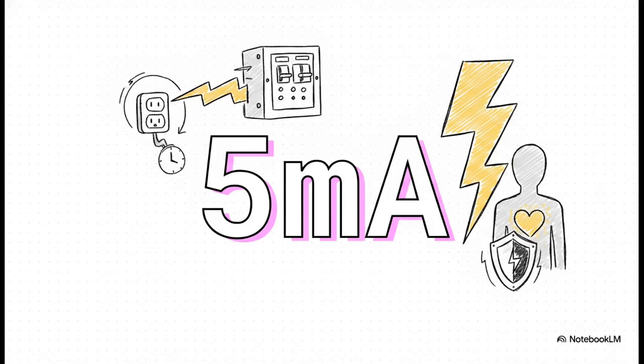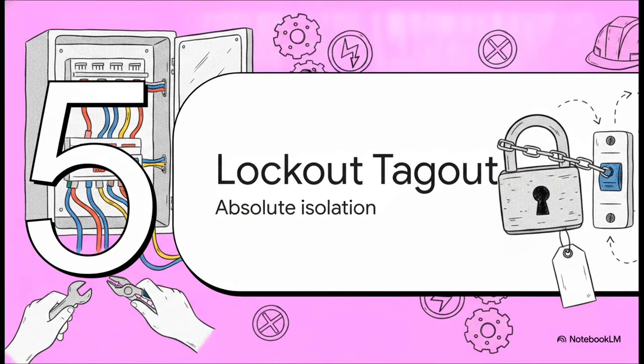GFCIs don't replace breakers, and they for sure don't replace safe work practices, but they are a vital layer of defense specifically designed to protect the human body. As amazing as those automatic protectors are, we really can't rely on them when we're intentionally exposing wires to perform maintenance. When professionals open electrical panels, they rely on absolute manual isolation. That brings us to our final section, Section 5, Ultimate Safety, Lockout Tagout, Absolute Isolation.